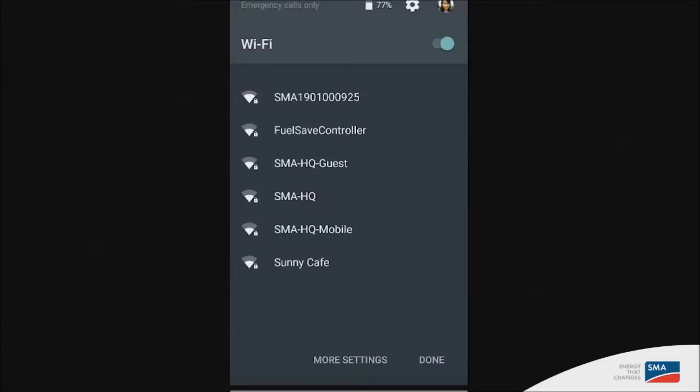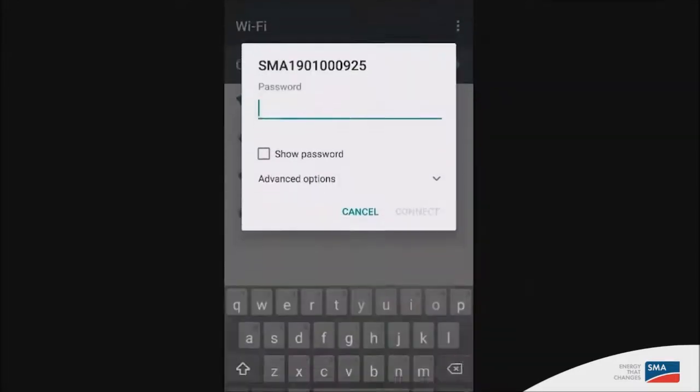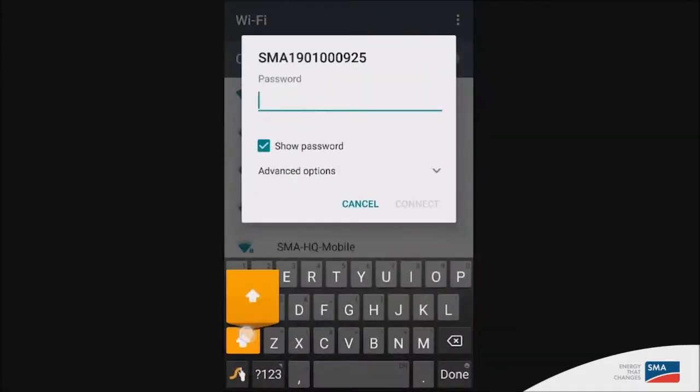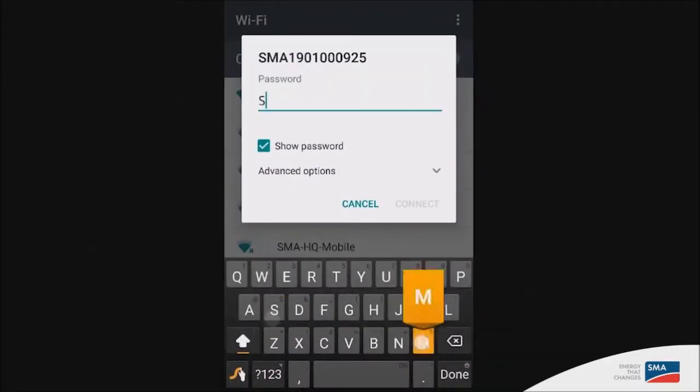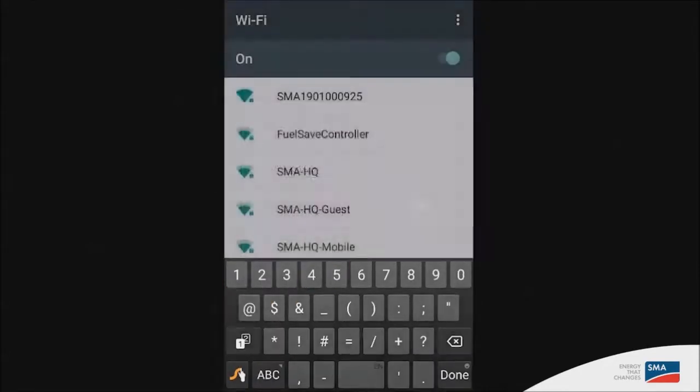It will be in the format of SMA followed by the serial number of the inverter. The first time you access the Wi-Fi interface, the password you need to use is SMA12345, ensuring that S, M and A are in capital letters.